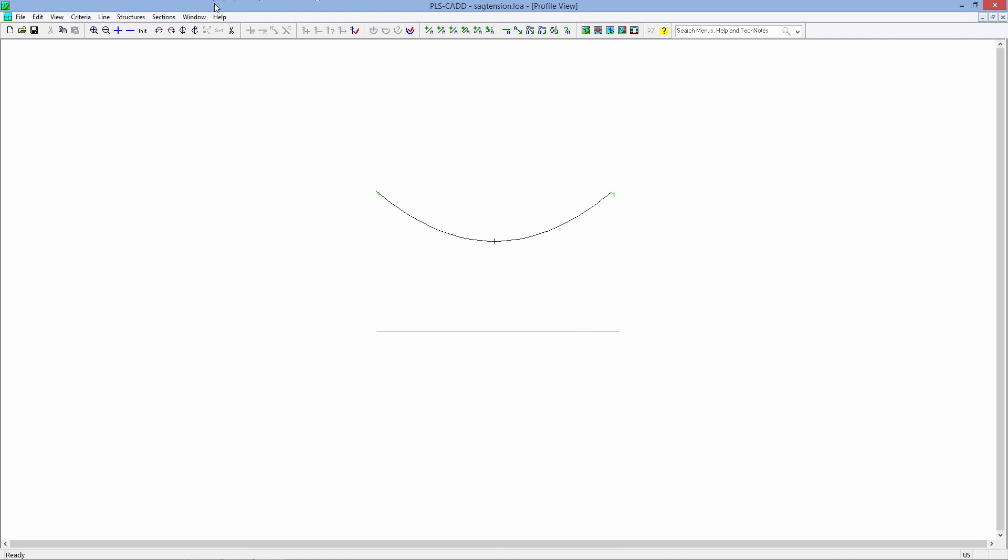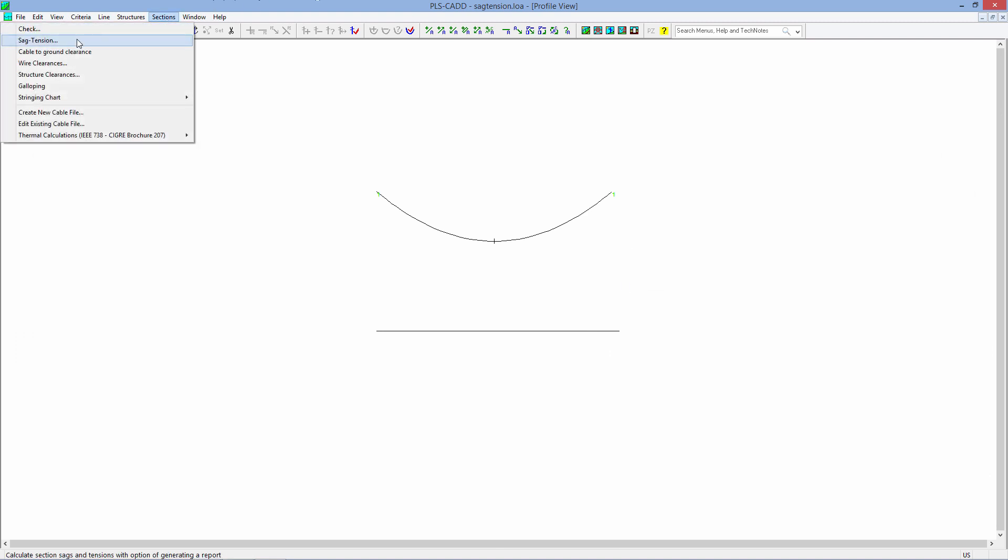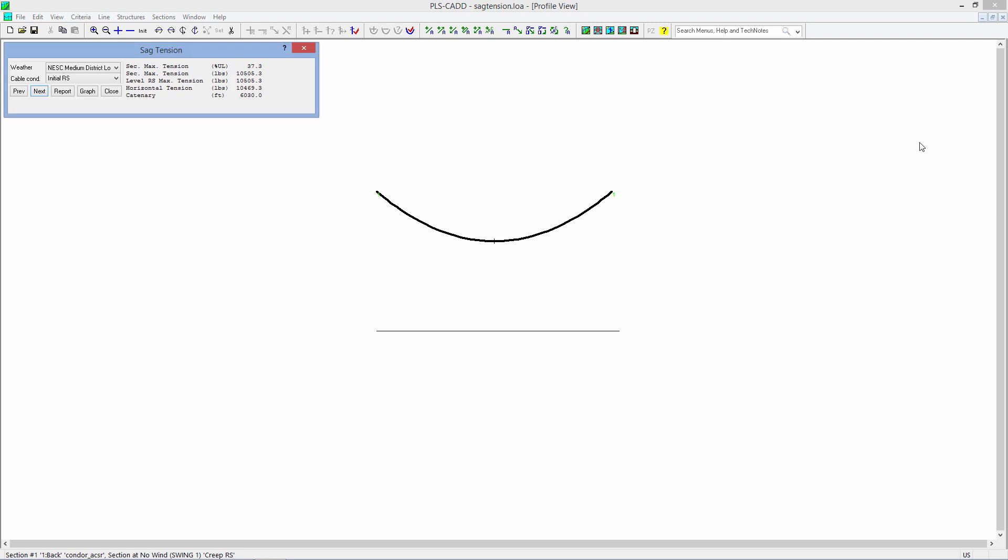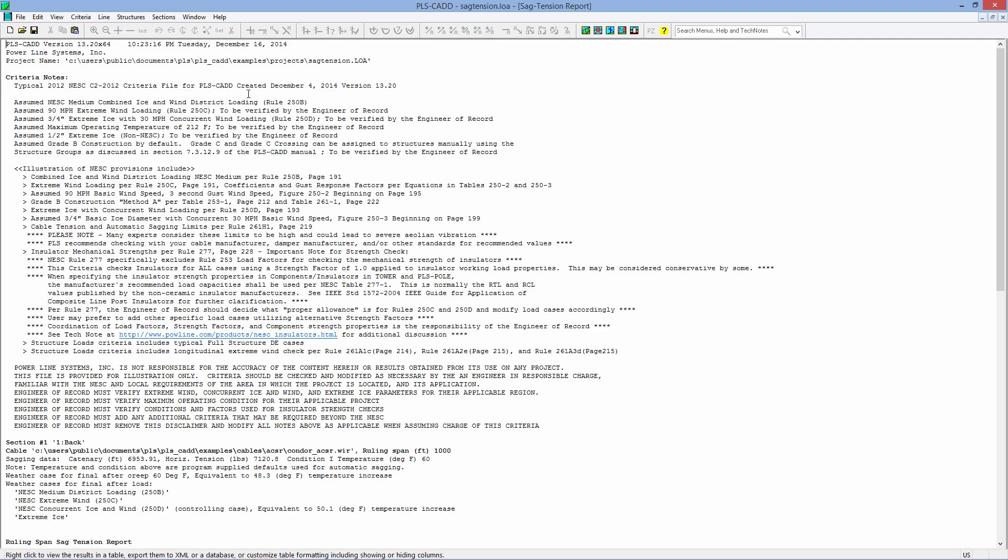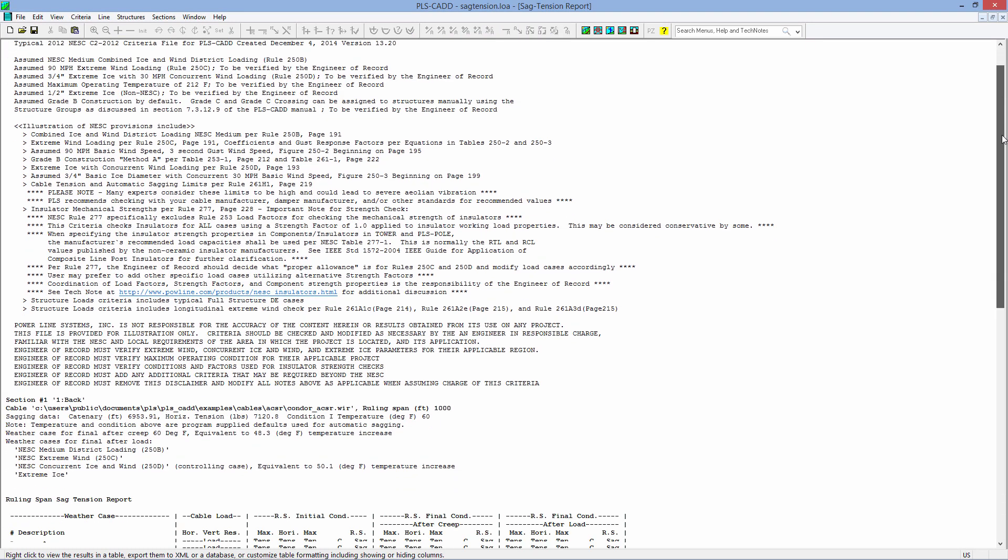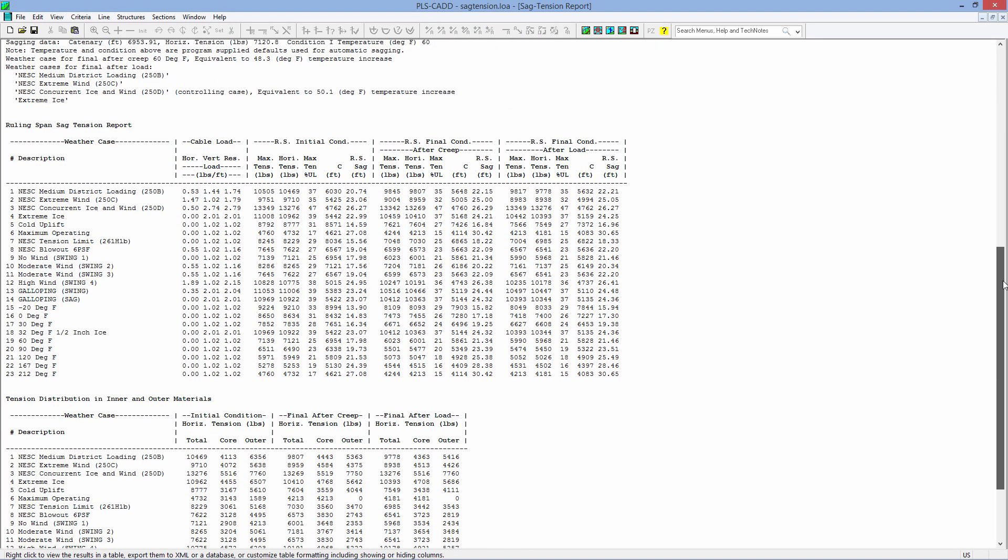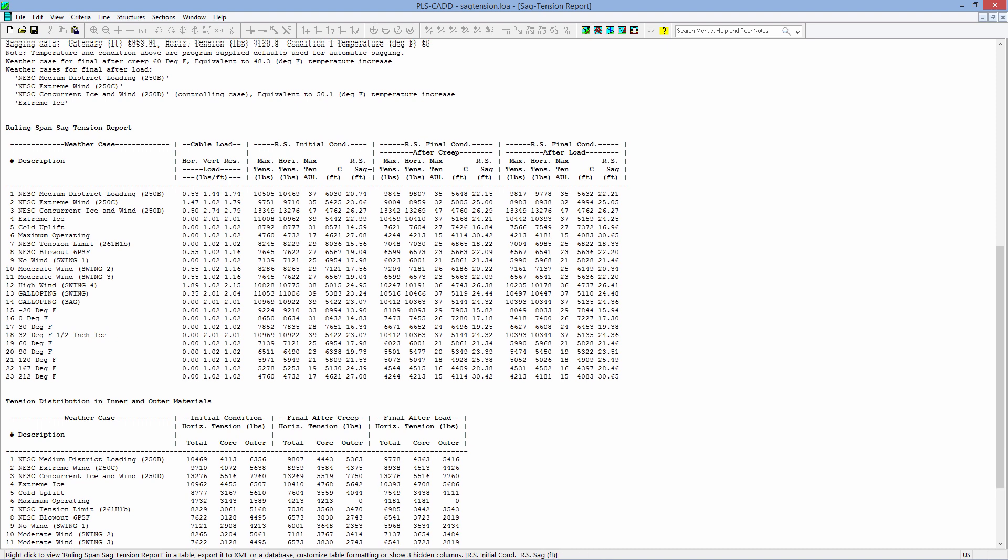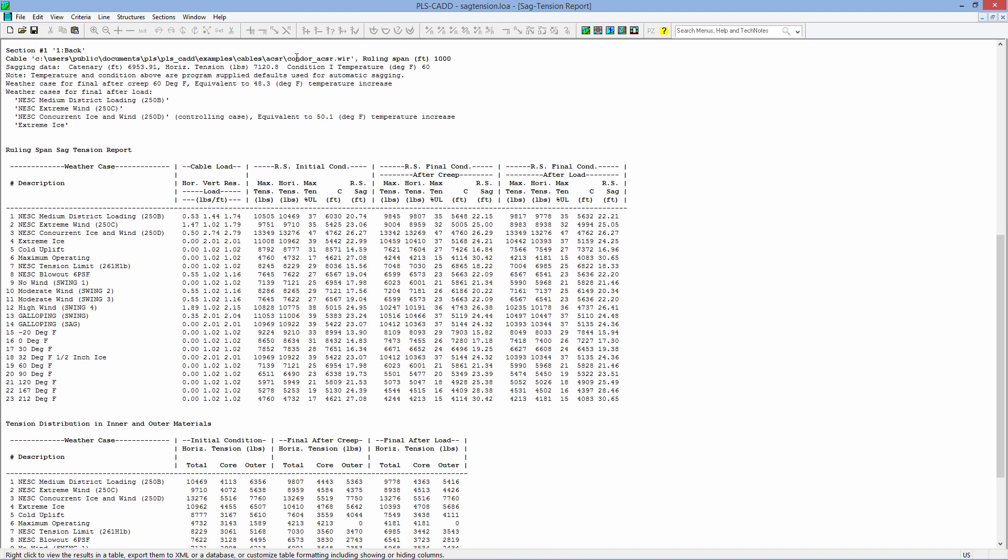We have a longer span, and if you want to generate a new sag tension run, Sections, Sag Tension. And we'll click on the Report button to get the full report, and this is the full report of the sag tension with our Condor ACSR with a 1,000-foot level ruling span.